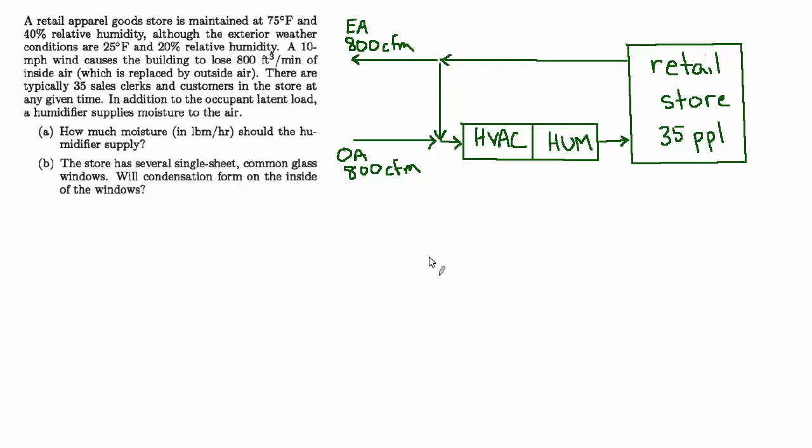So I've drawn on the right a simple air handling scheme. We have the retail store with about 35 people in it at any given time, and then we have this exfiltration that's causing the building to lose 800 CFM of inside air on a continuous basis. I've drawn that as exhaust air.